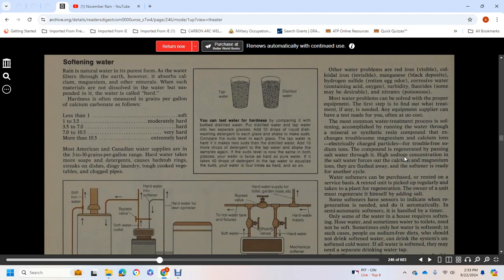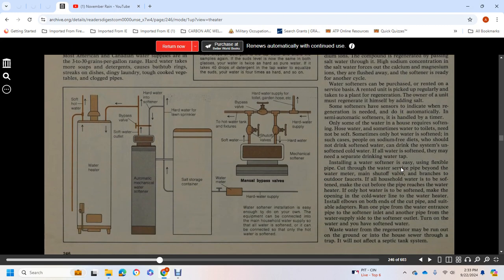The first step is to find out whether treatment is needed. Any equipment supplier will have tests made, often at no cost. The most common water treatment process is softening, accomplished by running the water through a mineral and synthetic resin compound, which exchanges the troublesome magnesium and calcium ions, electrically charged particles, with trouble-free sodium ions. It is regenerated by passing salt water with a high sodium concentration through it, which forces out the calcium and magnesium ions, flushes them away, and the softener is ready for another cycle.